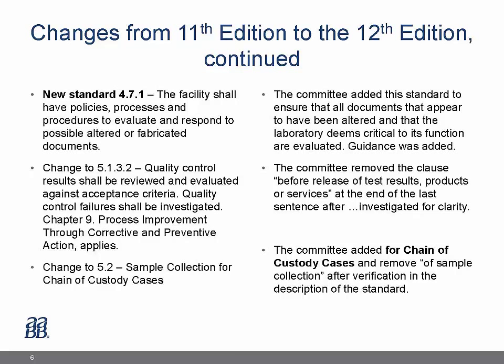The next change was to 5.1.3.2: quality control results shall be reviewed and evaluated against acceptance criteria, and quality control failures shall be investigated. Chapter 9, process improvement through corrective and preventative action, applies. The committee removed the clause 'before release of test results, products, or services' for clarity — oftentimes all of the investigation cannot be completed before test results have to be released. We also added the reference to Chapter 9 corrective and preventative action to this standard.